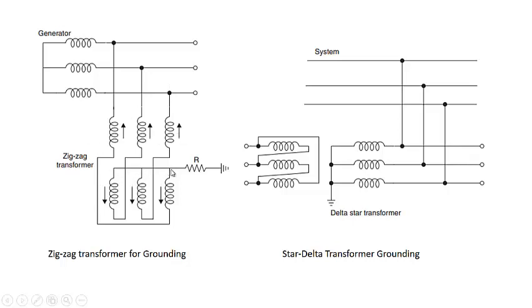And this is the neutral point of the system. This connection over here is the neutral point of the system, and when such cases occur, we can use this as a neutral. If we don't have a zigzag transformer, we can use a star delta transformer over here to take the neutral of the system, or to make the neutral of the system available.